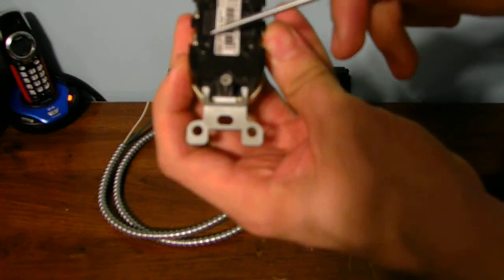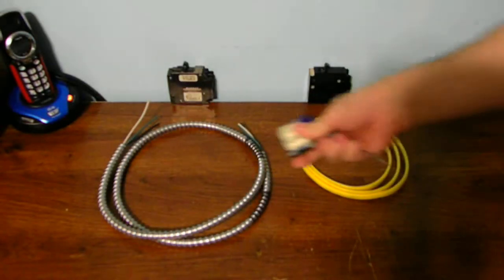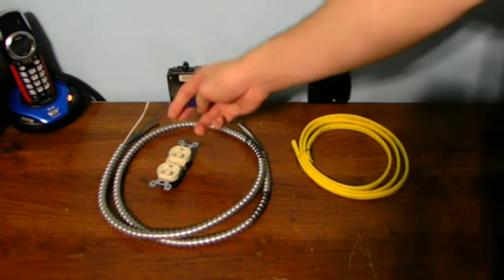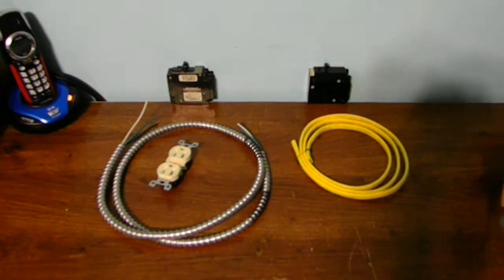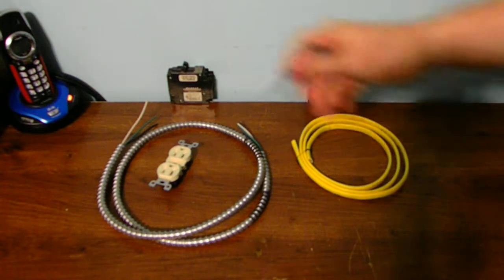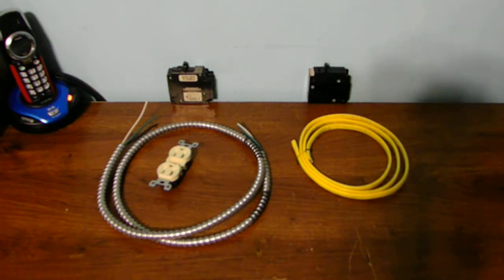On the back we've got these absolutely disgusting push-in connectors. Never ever use these connectors on the back of the outlet. This would typically go with a 14 gauge wire. If I had a 20 amp plug I would put it here, but I don't have one.